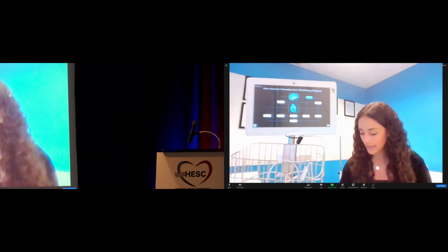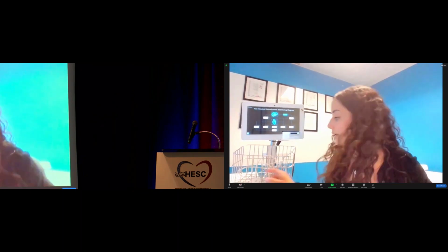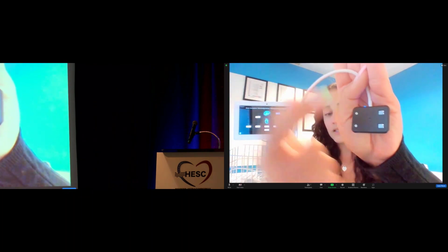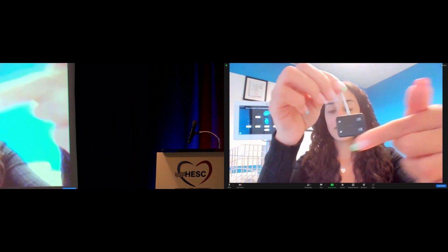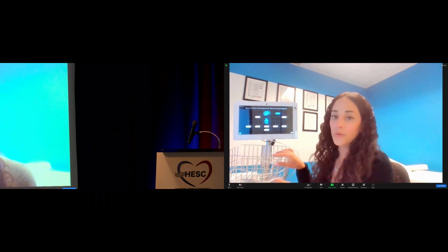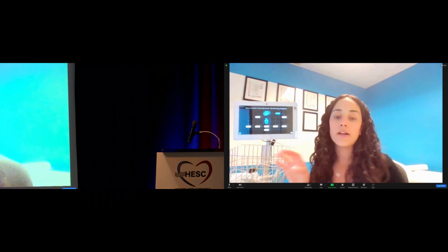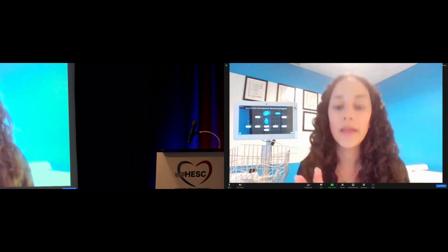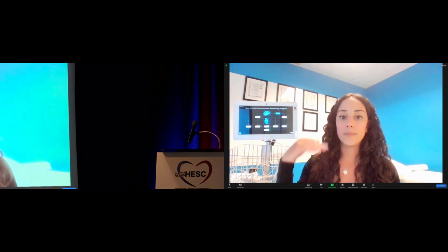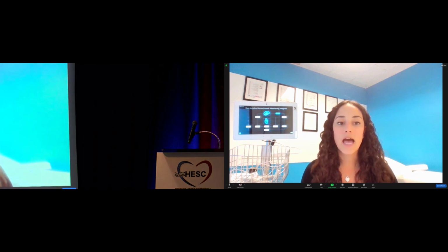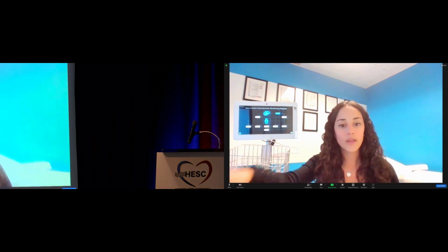So to take a closer look at the sensors, over here we have photo emitters and photo detectors. So these are our photo emitters, and then these are our photo detectors. And they're placed in this configuration to provide a radial scan of the data points, so that when we're penetrating and trying to understand or calculate the oxygenation levels, we're getting a broader scope.